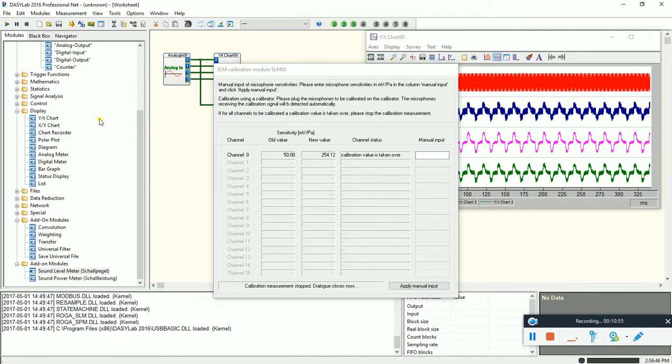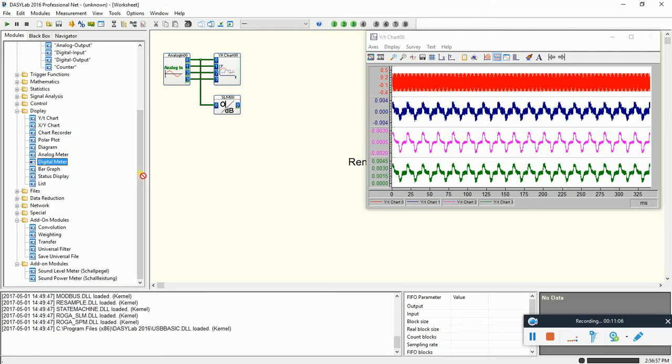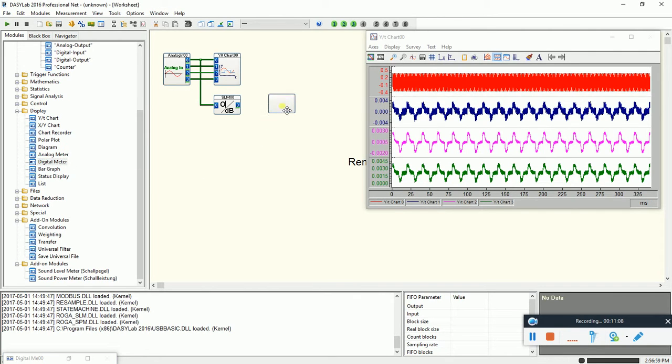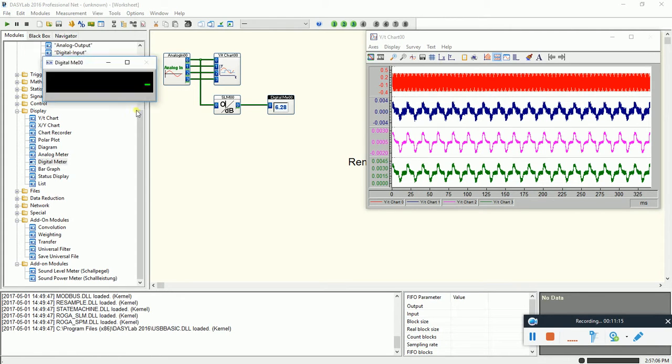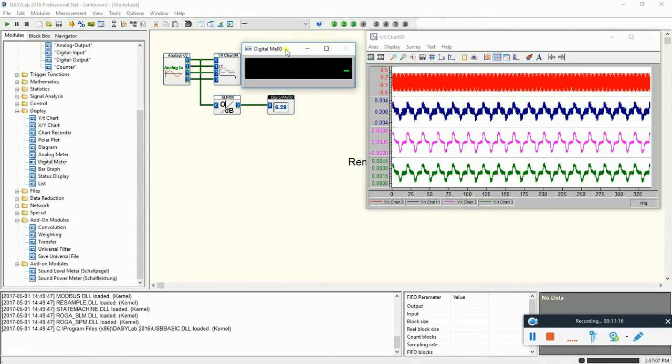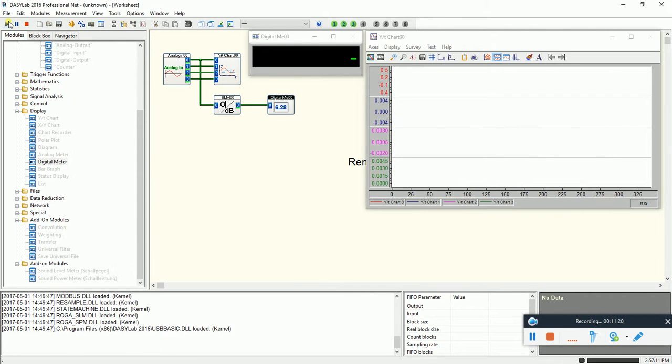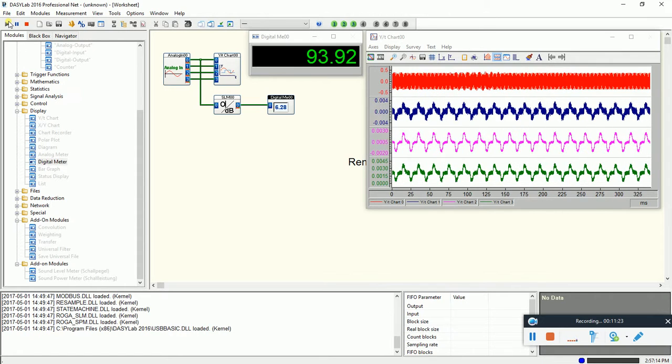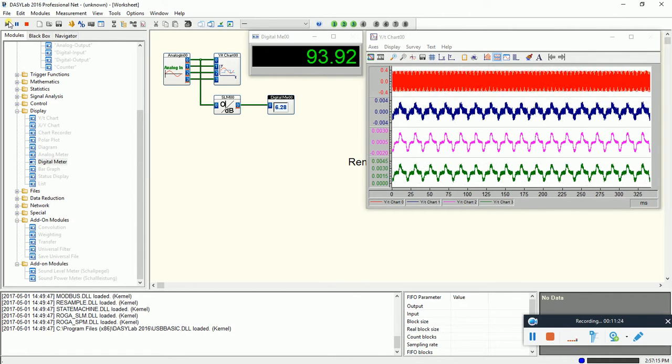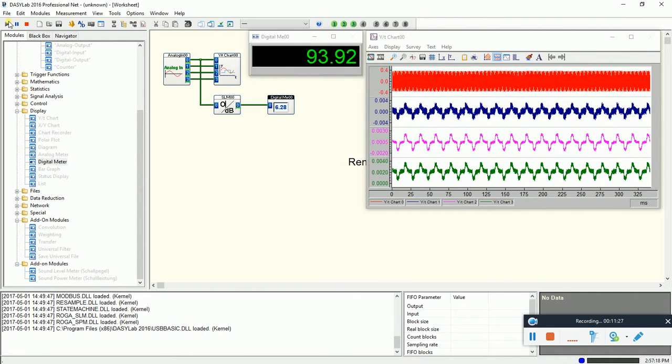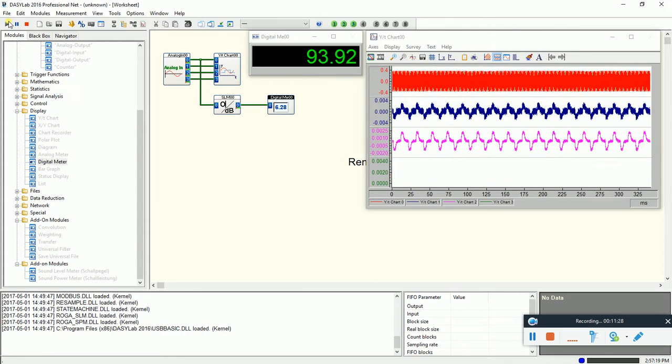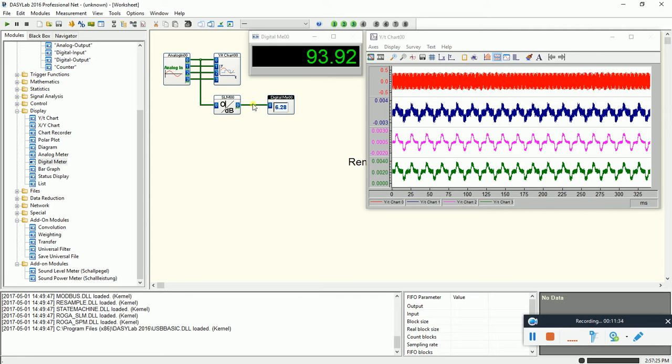The calibration is done. Here I can connect. We like to see the signal, of course I can connect here a digital meter. Just see, let's see. 93.94 dB. So now the output of this one is calibrated.